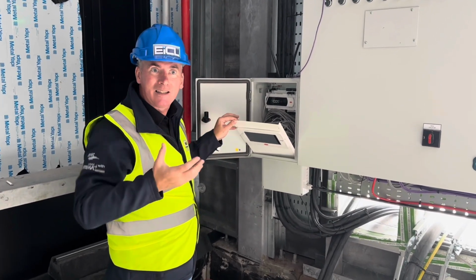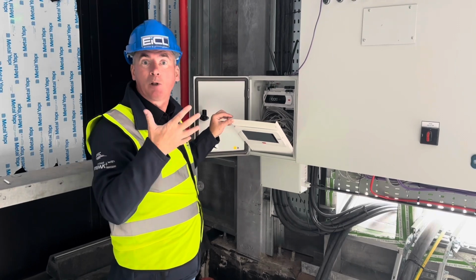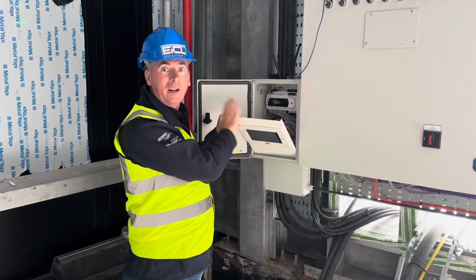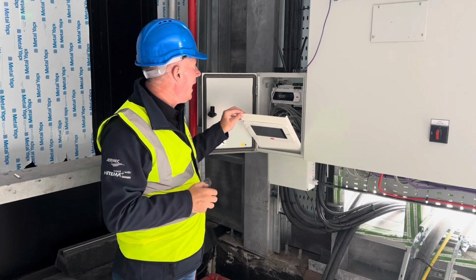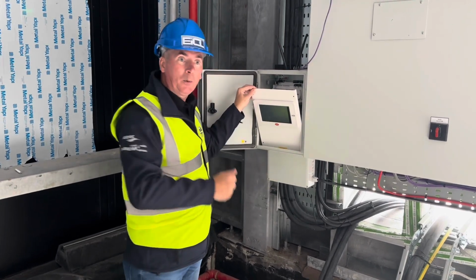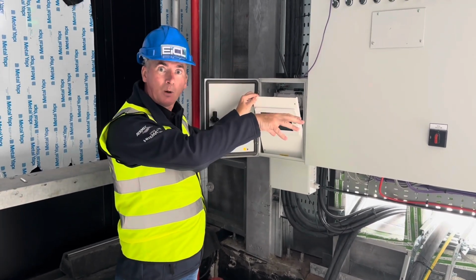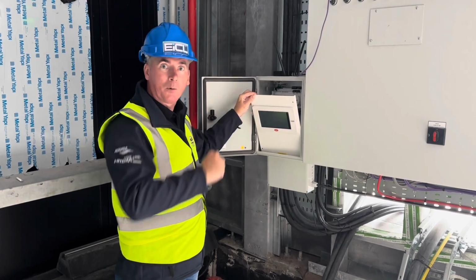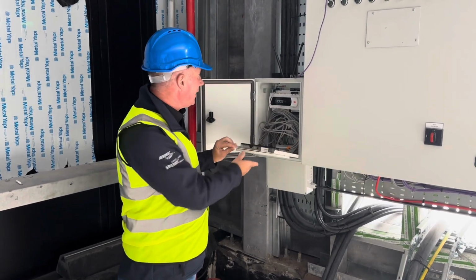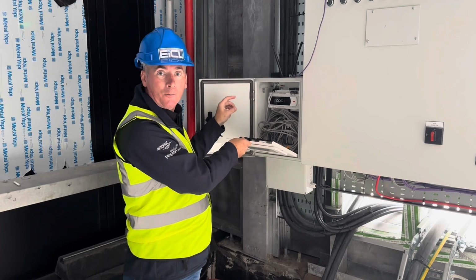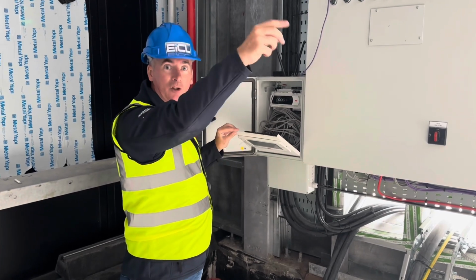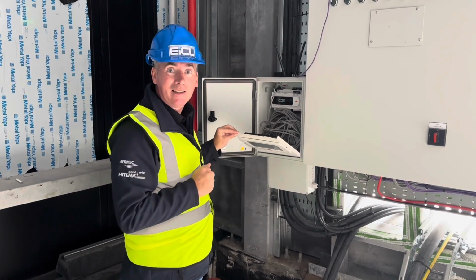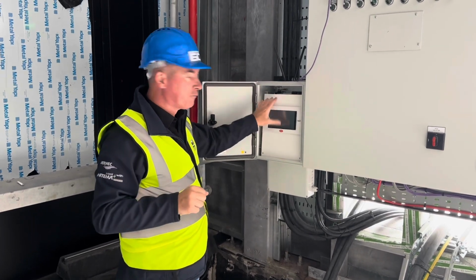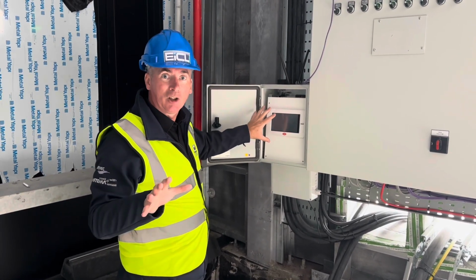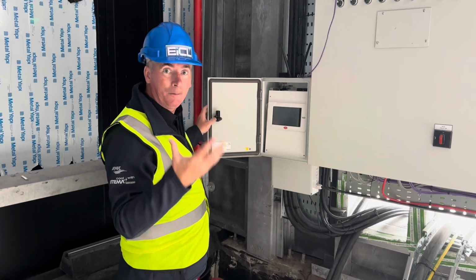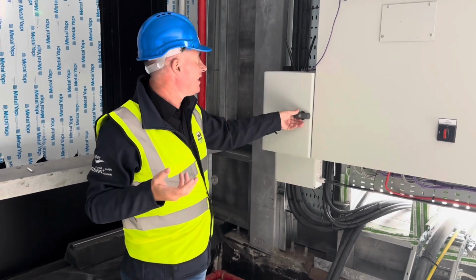So any system that has 2 or more chillers, heat pumps, or multifunction heat pumps, this really is a no-brainer. It pays for itself in no time at all. You will need the expansion board, by the way, if the probes tend to be a lot further away, or if this unit is very far away from your controller. It's very simply connected to a serial interface, an RS485, that communicates with each unit, and it's just simply connected in series. So it's a really good component, very much a game changer with regards to optimizing the efficiency of, like I said, 2 or more units on the same hydronic system.